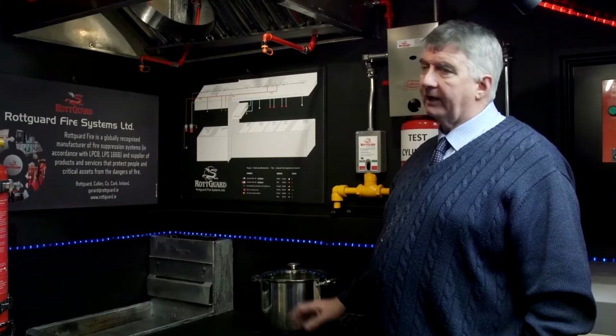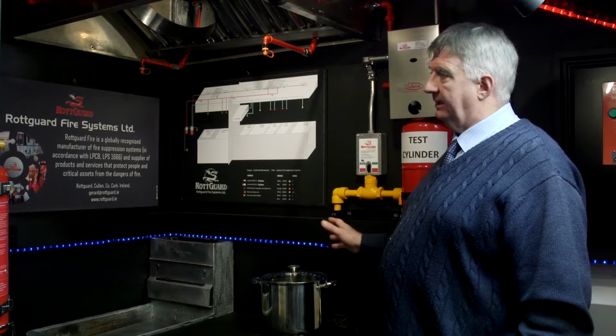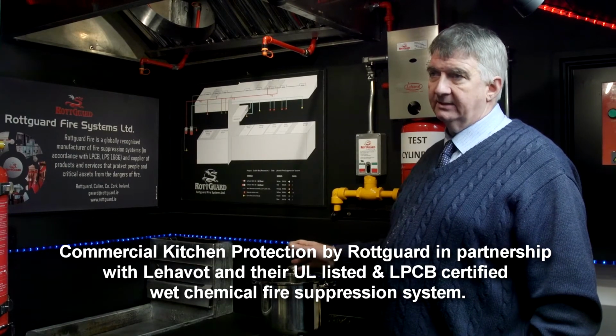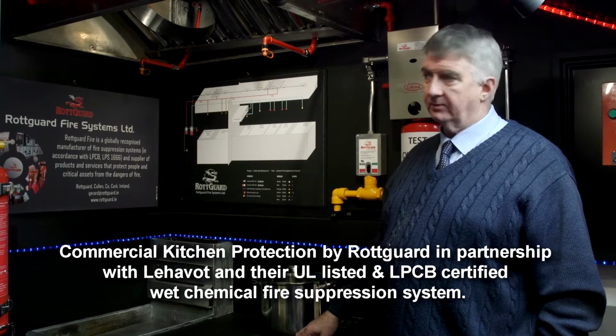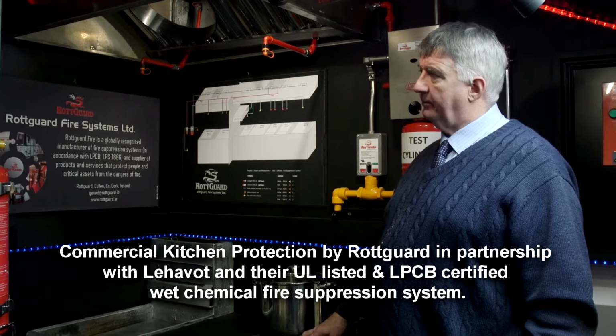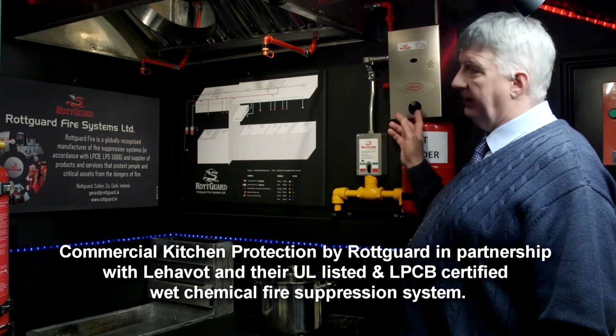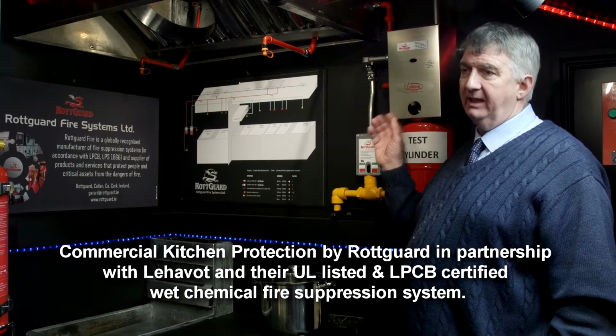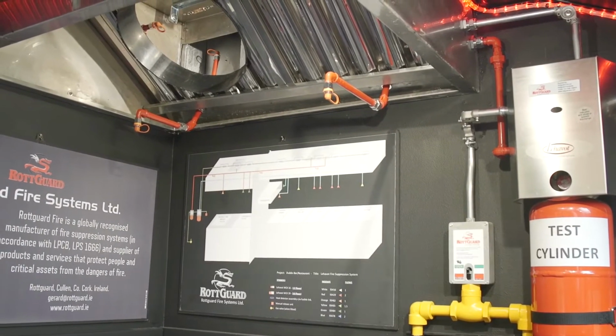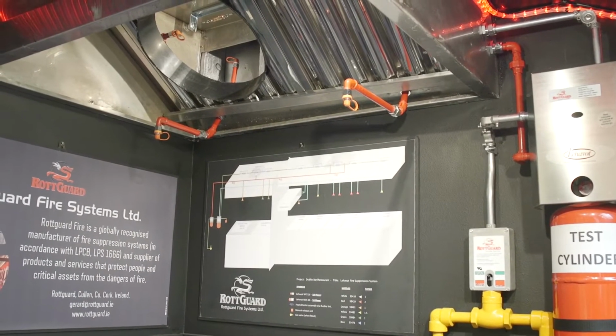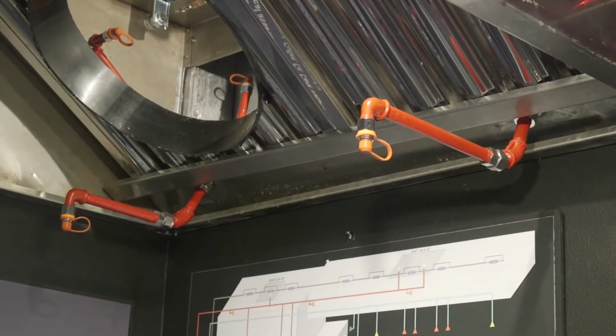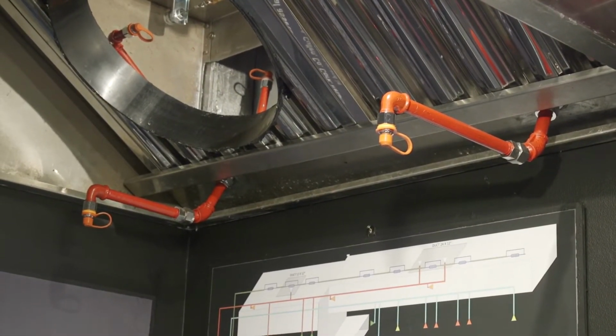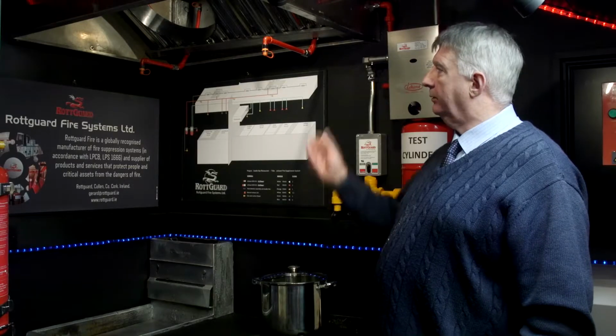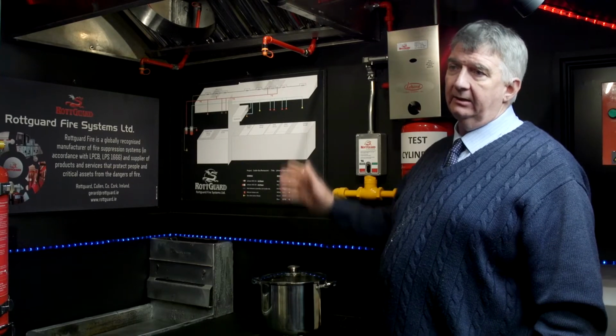This here is representative of a wet chemical system used for the protection of commercial kitchens. Rottguard are the Irish agents for this Lehavot system. It is UL listed and it is certified by the Loss Prevention Certification Board. It's a very good system compared to others in that it is spring loaded, it requires no cartridge, which means less maintenance. All the nozzles are color coded so that any fire officer or insurance agent can look at it and determine from a checklist whether the system has been designed properly, whether all the nozzles are in the right position and at the right height.